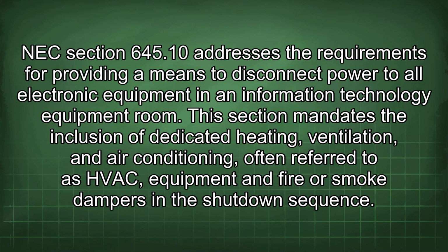NEC Section 645.10 addresses the requirements for providing a means to disconnect power to all electronic equipment in an information technology equipment room. This section mandates the inclusion of dedicated heating, ventilation, and air conditioning, often referred to as HVAC equipment, and fire or smoke dampers in the shutdown sequence.